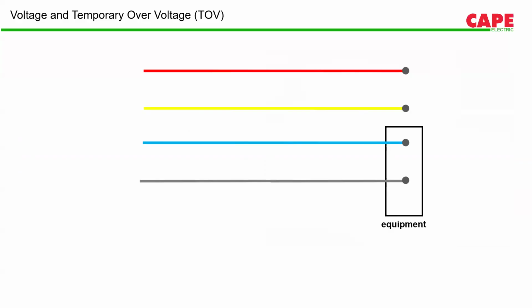Now, temporary overvoltage conditions. Earlier I also used this word TOV while talking about MOV failures. As Mr. Anandu has told, voltage protection level of an SPD is the voltage at which an SPD starts to operate or react. Generally, the voltage protection level of a 4+0 connection SPD is around 1.5 kV, whereas in a 3+1 SPD it is generally 1.5 plus 1.5, around 3 kV. That means an SPD will operate somewhere near 1.5 or 3 kilovolts. Whenever there is a surge of 1.5 or 3 kilovolts, the SPD will operate.